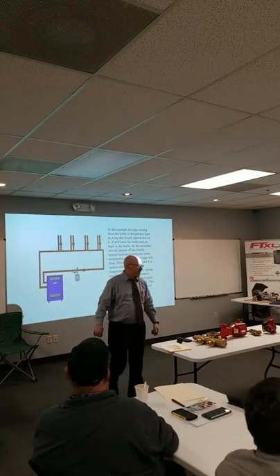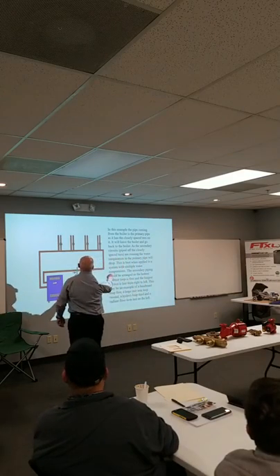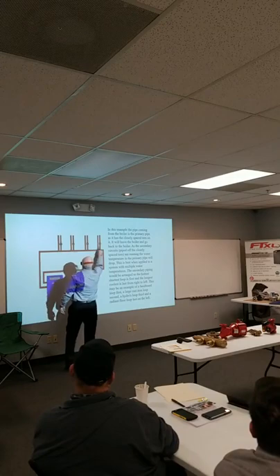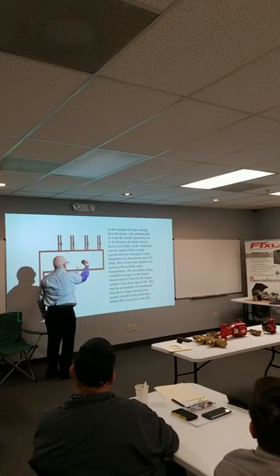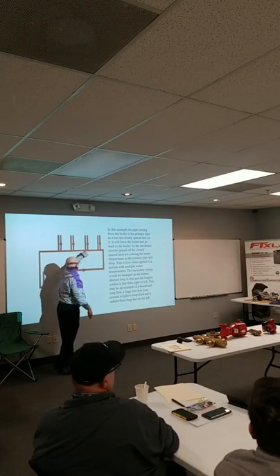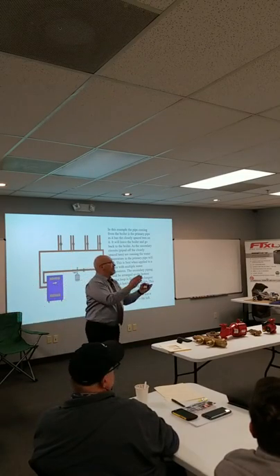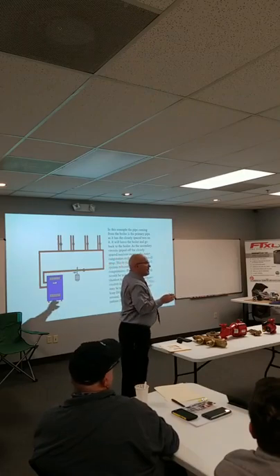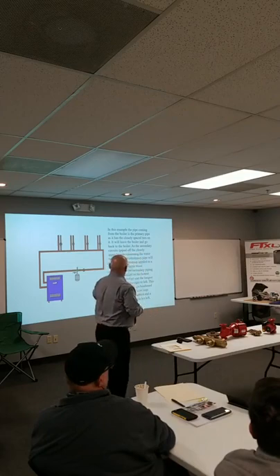You showed the flow going down the big pipe. Show me where the flow should go on the secondary. So that arrow, you can't see it probably, but that arrow is pointing up. So I want to pump into my zone, through my zone, and then it returns here, just downstream of where it took off. Yes. On the primary. 4 pipe diameters. Right. Same principle. Yeah. 4 pipe diameters max on a decoupler. When you do it this way.